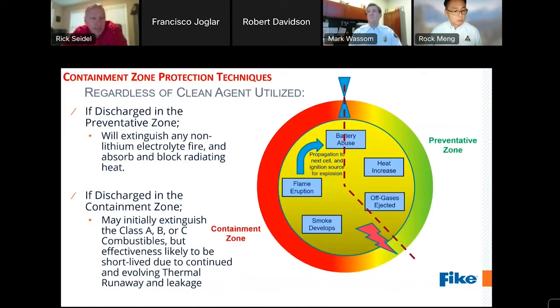Regardless of the clean agent utilized, if it's discharged in the preventative zone, we will extinguish any non-lithium electrolyte fire and will provide a level of absorption and block radiating heat that may be coming from the event as it's escalating. But if it's discharged in the containment zone, it may initially extinguish the class A, B, or C combustibles, but the effectiveness for long-term fire protection is likely to be short-lived due to continued and evolved thermal runaway and leakage from the enclosure. Next, please.